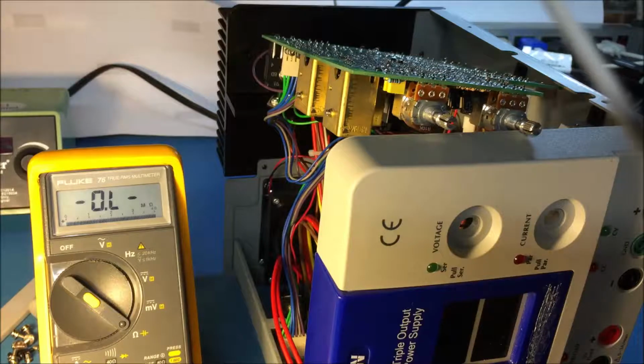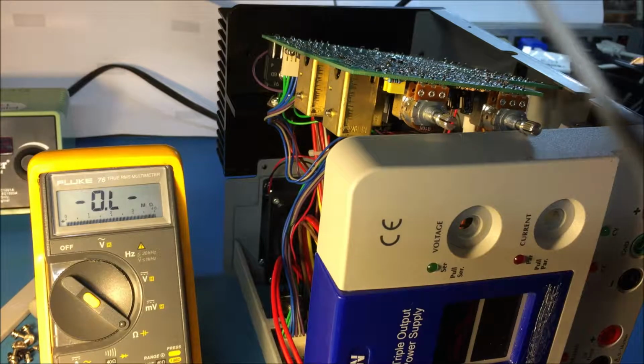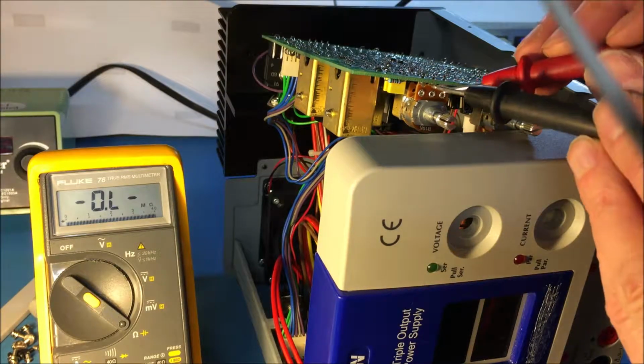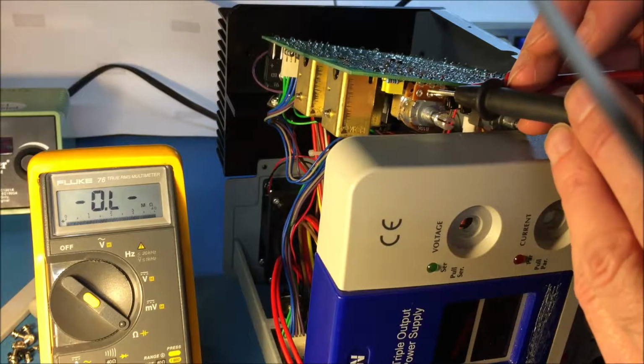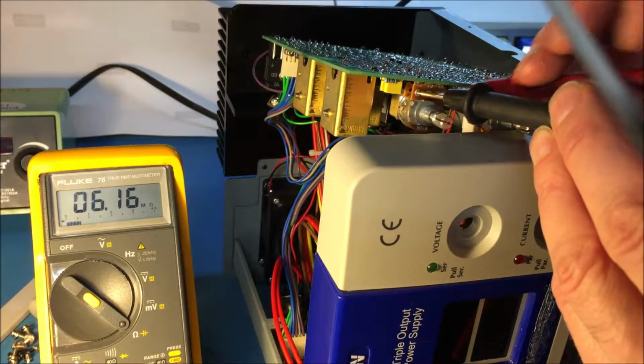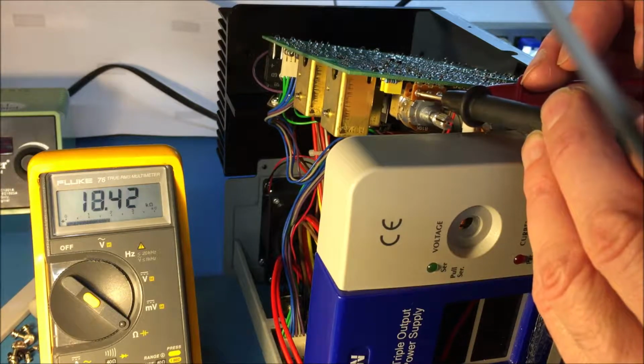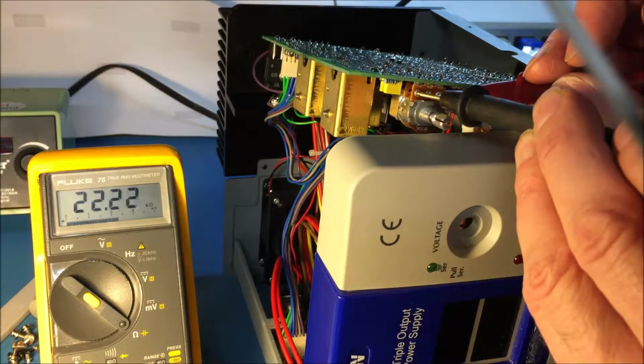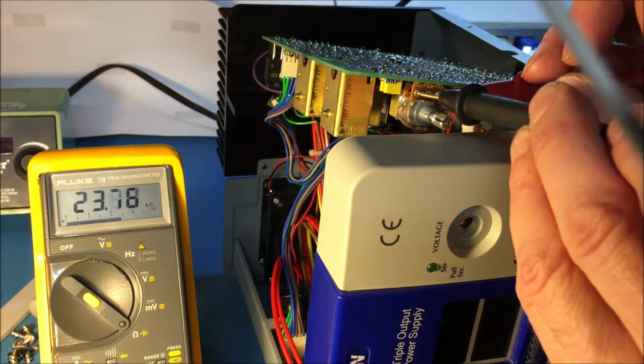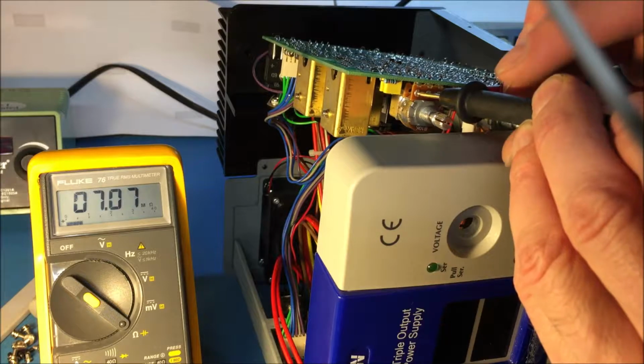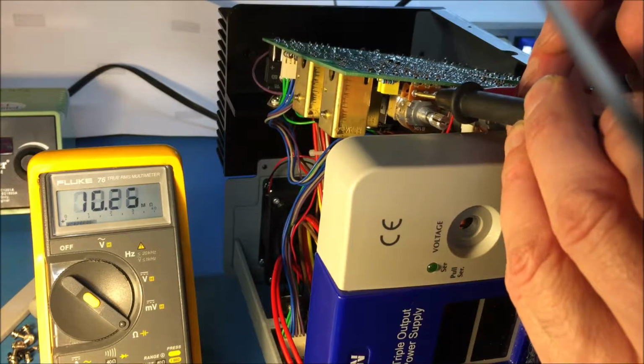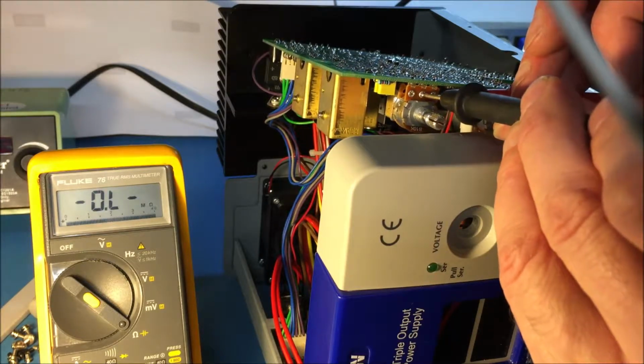To check the potentiometer function, we use the probes on the multimeter set to resistance and put them on these lugs right here. The potentiometer should have a fixed value across the two lugs, and it appears that it's 22 kiloohms. But then between one lug and the wiper, it's showing megohms, so right there, that's showing a problem.